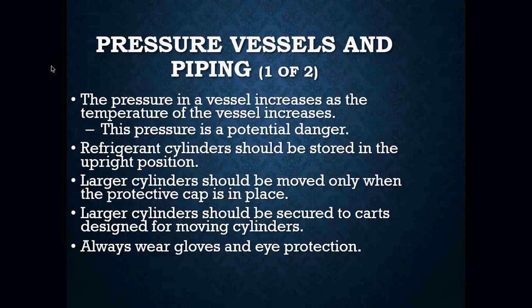If we're moving large cylinders, they should only be moved when that protective cap is in place. For example, a nitrogen cylinder - that protective cap should be on anytime you're moving it from point A to point B. Because what happens if you slip, or fall down a set of stairs? We're only human, we lose our balance. If we don't have that protective cap on, we can create a very dangerous situation.